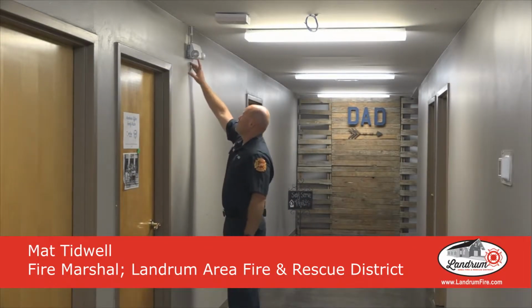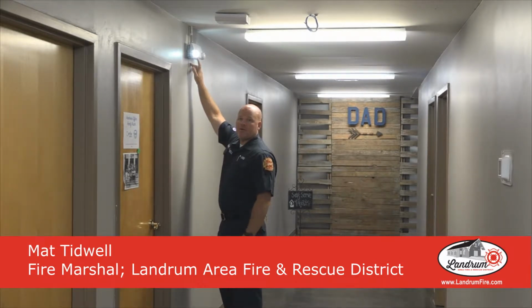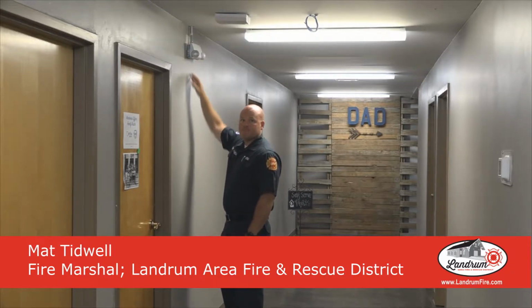All right, there's a small test button on these lights. I'm just going to press it and you see that the lights illuminate. This is simulating a power failure, and the lights illuminate so people can find their way out through the halls.